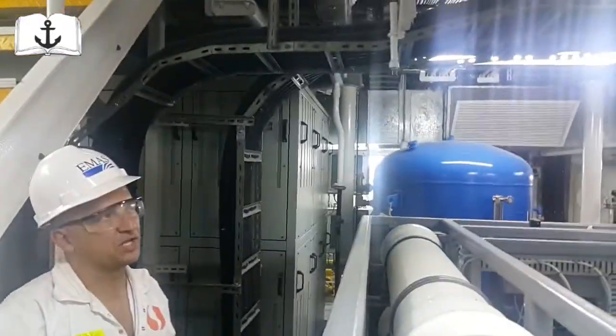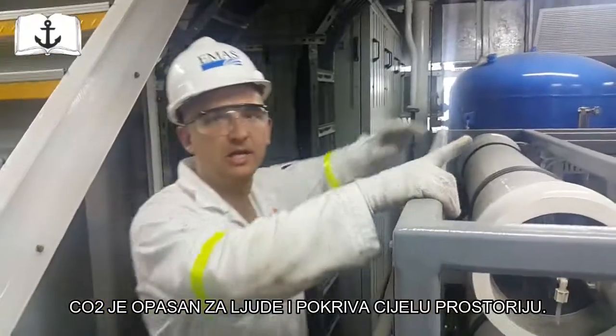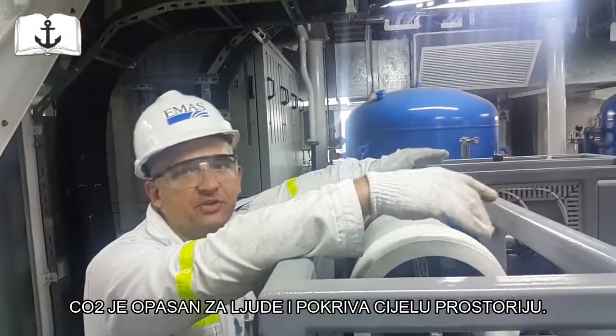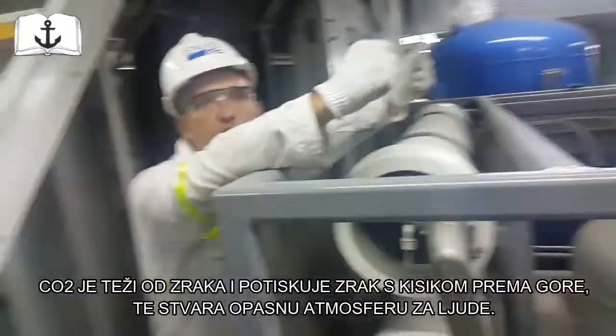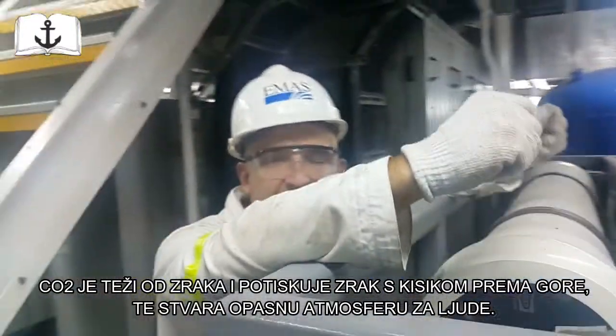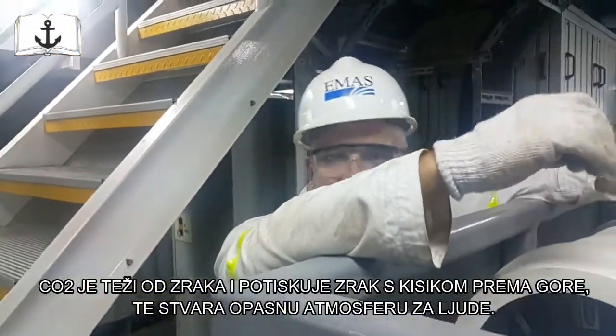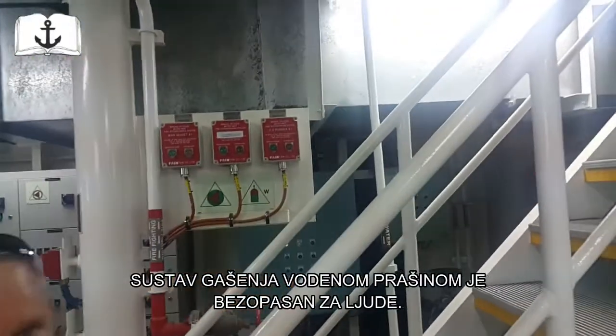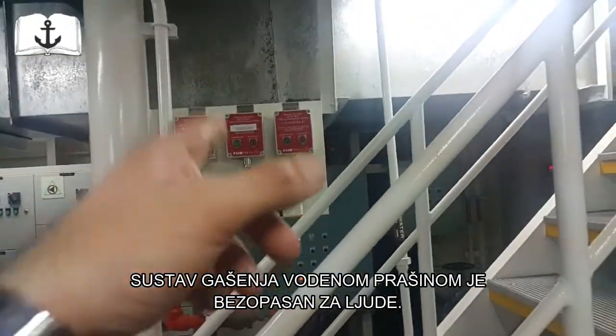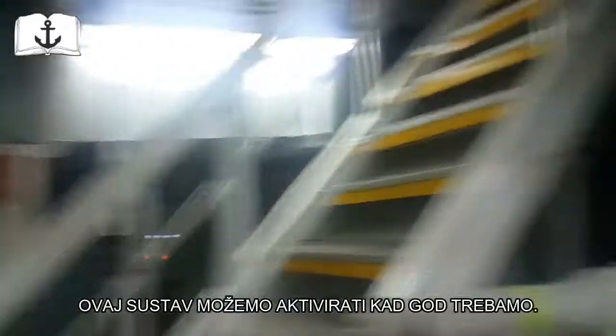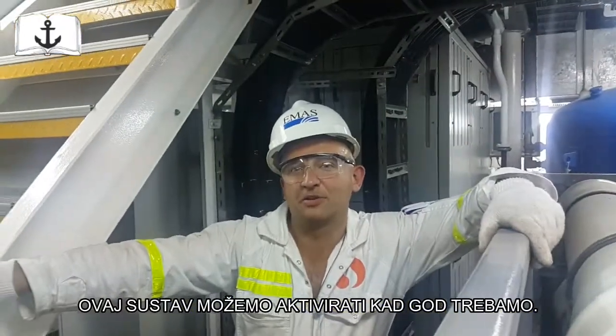Yeah. So the thing about the CO2 is that it will cover all the area and it's dangerous for the people because it's taking the oxygen out. And why are we taking out oxygen? Because we want to extinguish the fire. So this one, water mist, is harmless for people. You can activate it anytime you want.